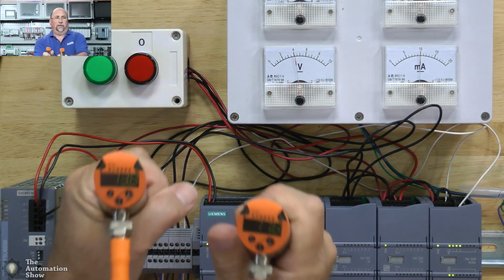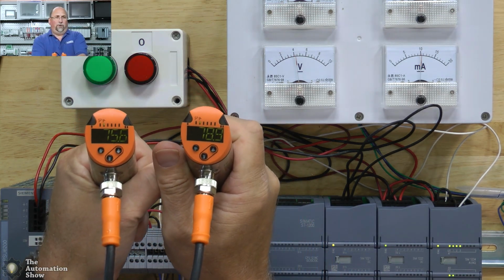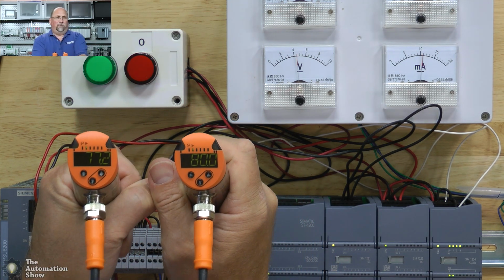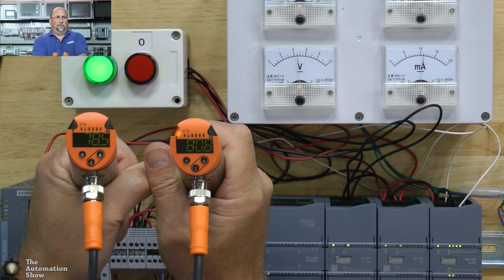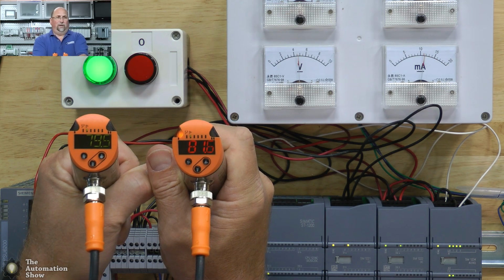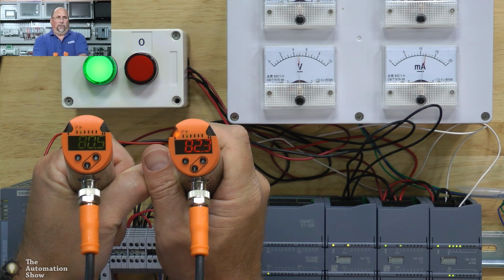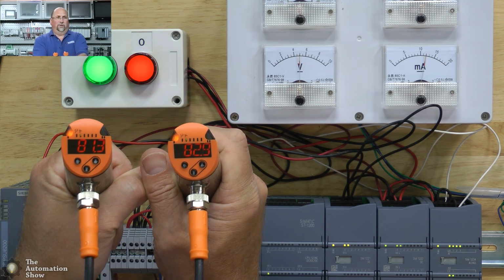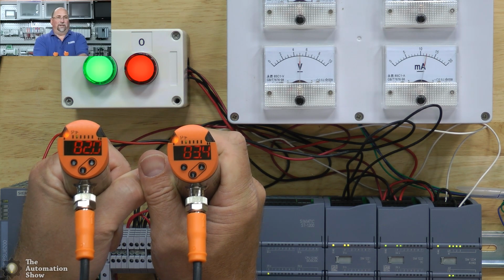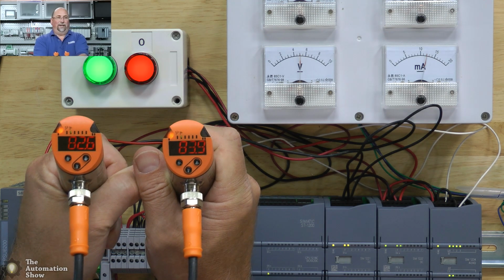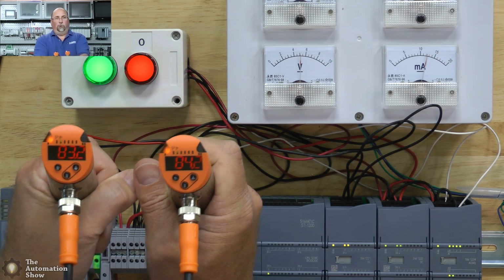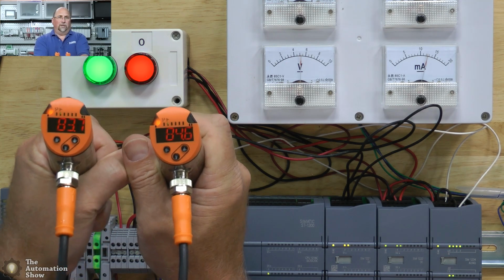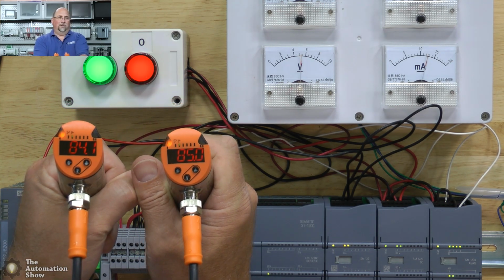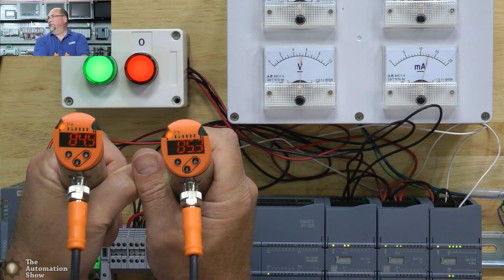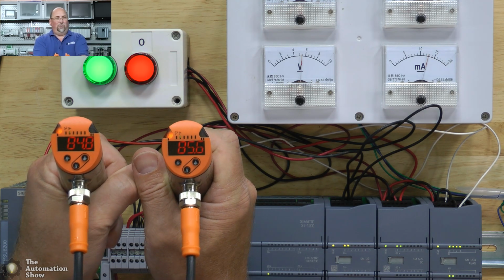Here, let's see if I can get them under the camera here. Get them all the way through the 65 to 80 range and all the way up into the 80 plus range when their outputs will come on. Yep, you see that? And you can see the meter's changing too because we're taking that analog in. One of these is current, one is voltage, and we're putting it to the analog outputs. Okay, and we can see that on the screen as well in our code.